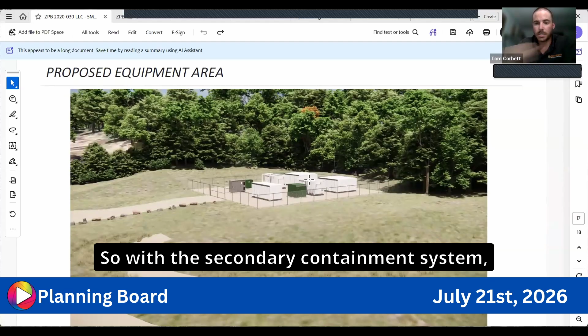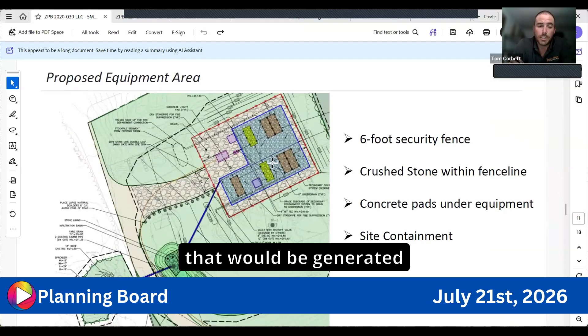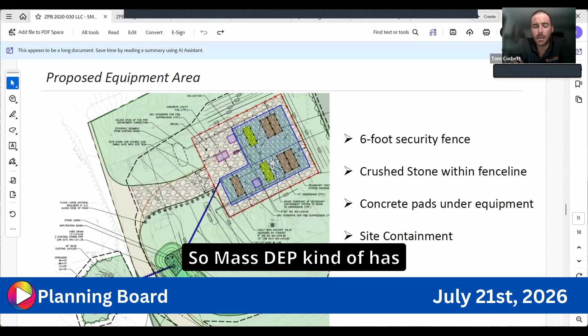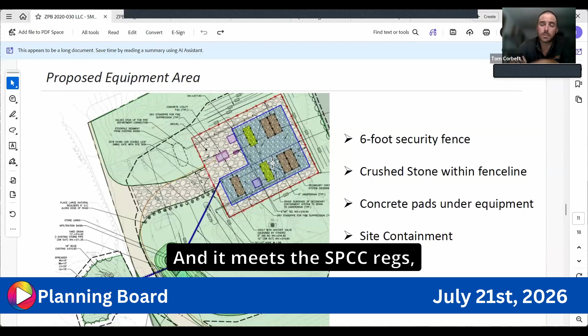With the secondary containment system, depicted here in blue, it's designed to capture and contain any water runoff generated during an emergency event at the site. Mass DEP has some standards around this, which we've drawn from other projects in the state, and we've landed on this as the suitable containment measure, similar to what's used on substations for oil-filled transformers. It meets the SPCC regulations, even though this project doesn't need to. So we're enhancing the containment on site.